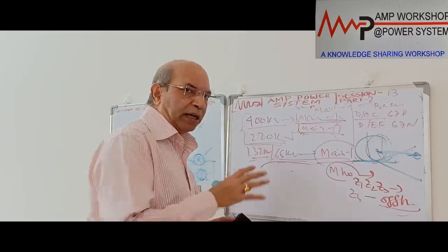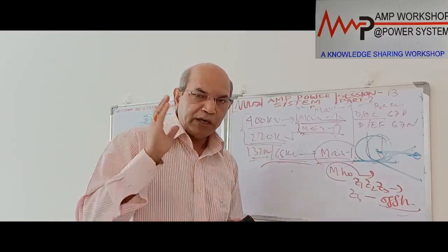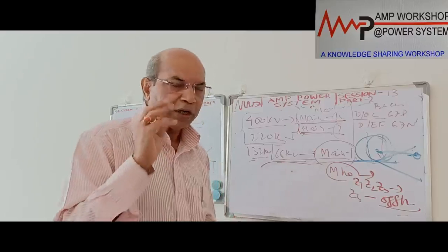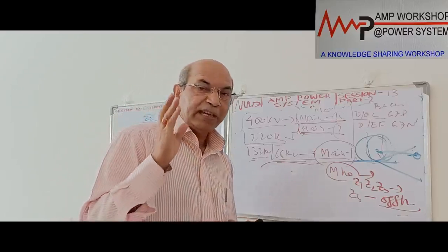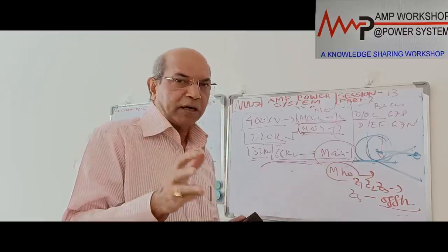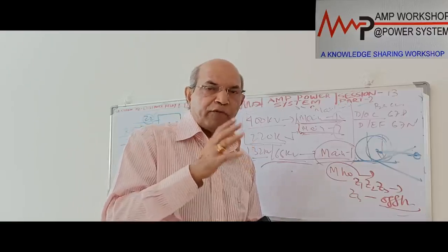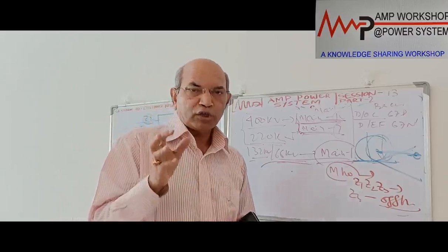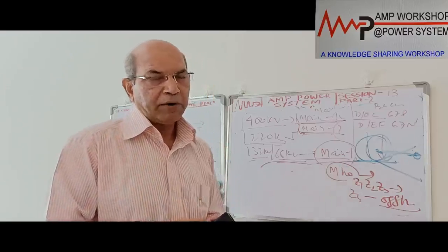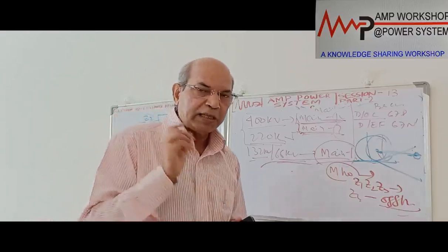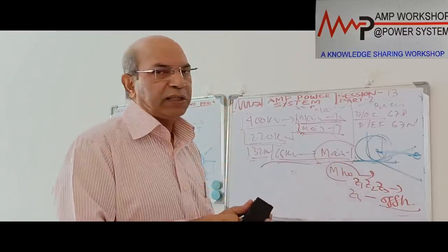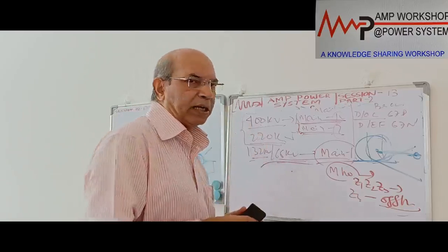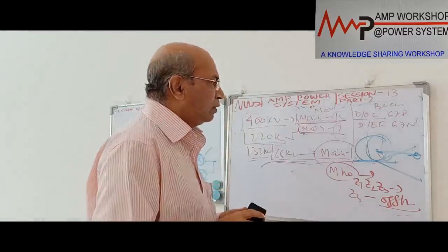Then all these relays should have independent indication for each zone, that is required, and the relay should have independent monitoring, and an event and disturbance recorder, pre-fault and post-fault waveforms of current, voltage and frequency, how they change. That recorder should be there. An event logger should also be there, all the events should be logged for our troubleshooting purposes, in the relay. So this is also required with the distance relays. So this is the brief specification. There are a lot of other issues which will be specified for the relay. So that is the practice more or less.